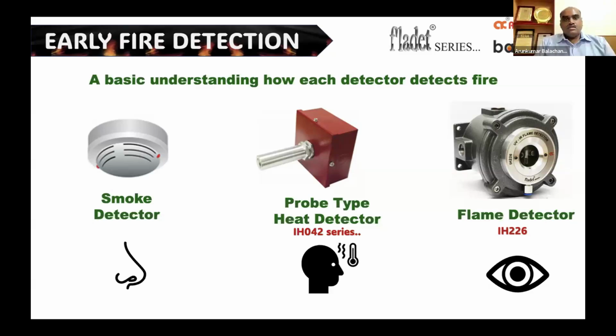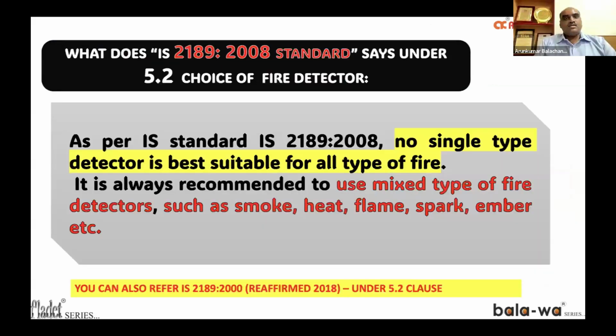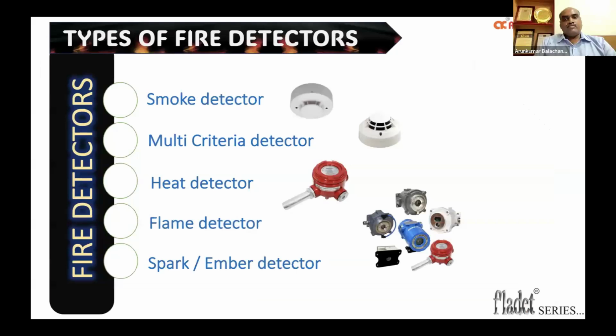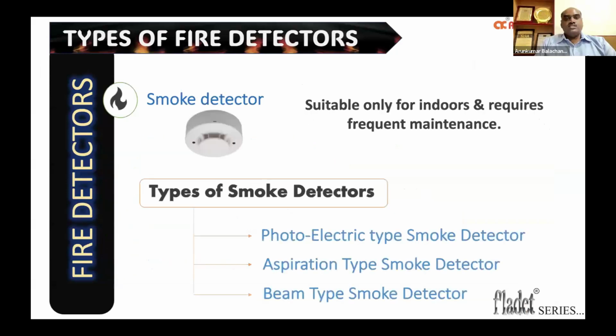So what does the standard say? The Indian standard IS 2189 clause 5.2 states that no single type of detector is best suitable for all types of fire. It is always recommended to use mixed types of fire detectors such as smoke, heat, flame, spark, or ember, etc. So coming to the types of detectors, these are the technologies available right now in fire detection: smoke detectors, multi-criteria detection, heat detectors, flame detectors, and spark and ember detectors. We'll go through each detector briefly.